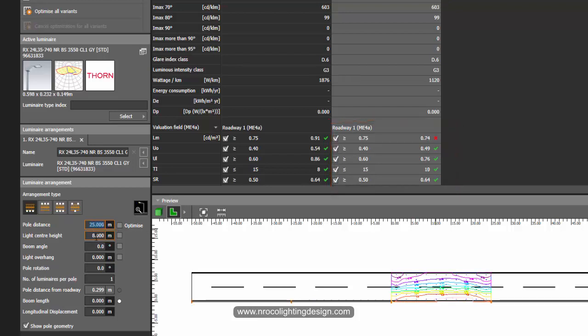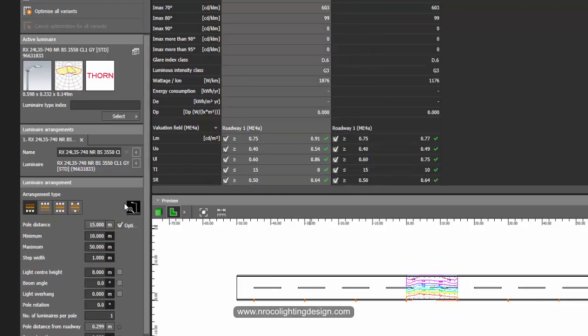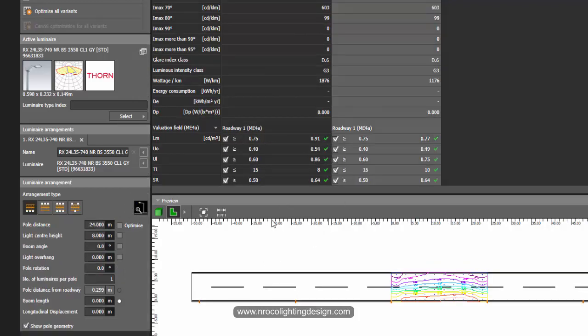This one is 15 meters apart of poles and this one is 24 meters apart of poles. What does it mean? This means that if you increase your maintenance factor you will have good savings in terms of the quantity of the poles and the quantity of the luminaires.